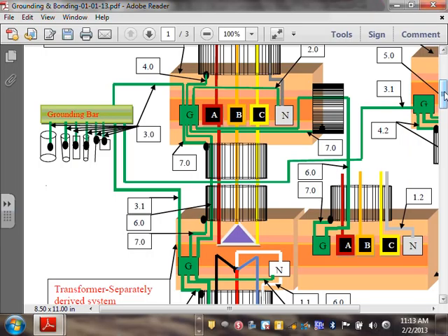Safety. The last thing you want to do is to take a phase of 208 and tie it to a neutral from 480, or vice versa, and get a weird high voltage that can burn equipment. Okay, so that's very, very important here. So here's my separate derived system. I have a transformer delta Y, I create a neutral.